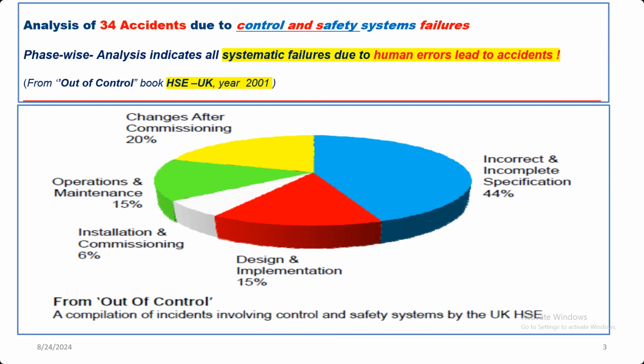I've been working on that in the late 70s in GACL, but nowadays most of the plants have DCS or PLC or some sort of computerized system, where safety and control systems are combined. Now, when you combine safety and control systems, as per the standard, it does not really improve the performance of the safety. That is why the failures are analyzed, and of these 34 accidents which were analyzed, they found that 44% of the accidents were due to incomplete or incorrect specifications.